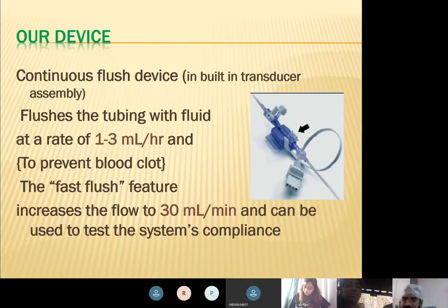Because if you keep it less than 120, less than 180, less than 200, there is a high chance that blood will come outside, and you know what blood does? It clots. The moment the blood clots, your line is gone. Once your blood has clotted, the diaphragm will no longer sense anything. If the diaphragm does not sense anything, you are not getting an arterial line. As simple as that. That is why it is an important responsibility of the doctors and the nurses to keep checking this.